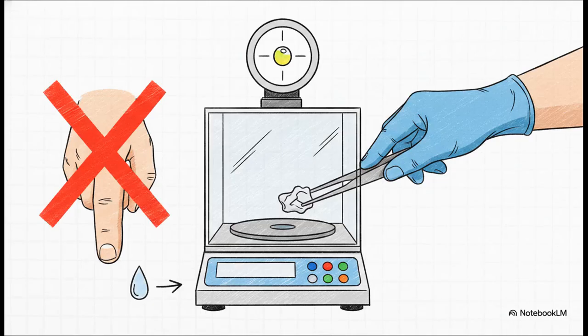Because these balances are so incredibly sensitive, the rules for using them are super strict. First, you have to ensure the machine is perfectly flat by checking the tiny internal spirit level. You hit the tare key to zero out the display. And here is a big one. You must never, ever touch samples with your bare fingers. You always use gloves or forceps. Even the microscopic amount of oil on your skin can completely ruin the perfect accuracy of these instruments.